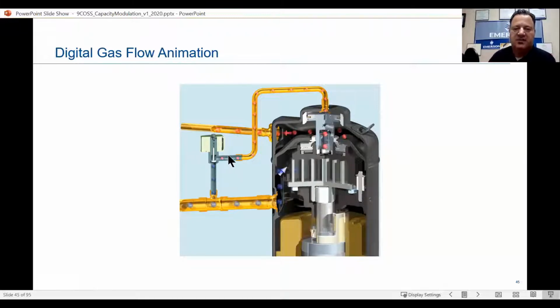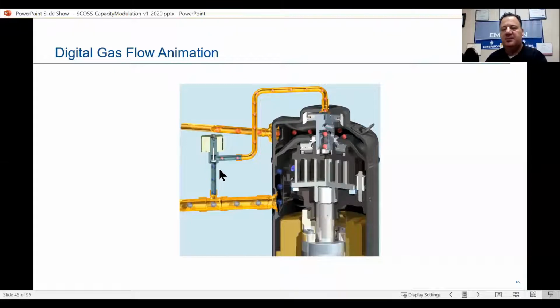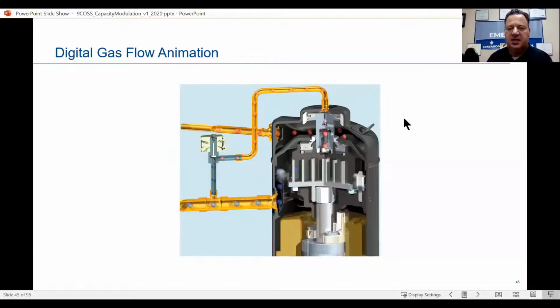Let's watch this solenoid valve again. There we've got electricity coming to the solenoid valve. It's calling, and now we're bleeding that off. So we're unloaded. Now we're loaded. Again, with the exception of air conditioning, the refrigeration is going to be in 20-second cycles. All right, 20-second increments. On air conditioning, that's going to change to 15 seconds. So it's going to unload or load four times a minute.